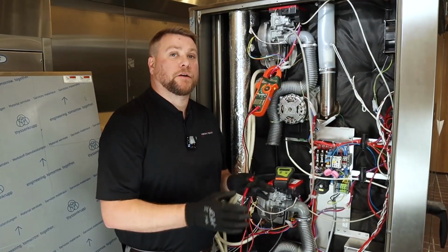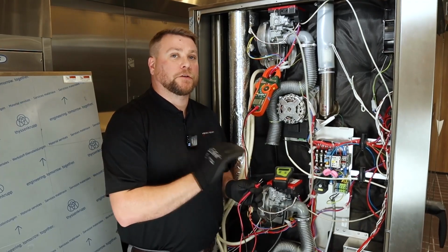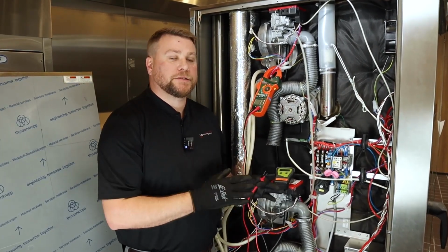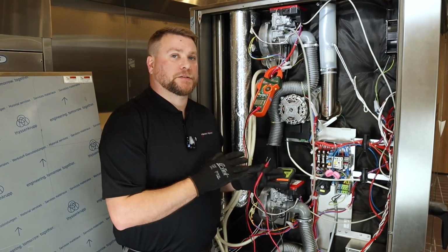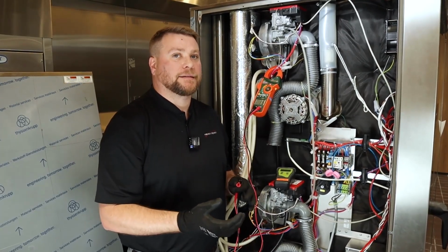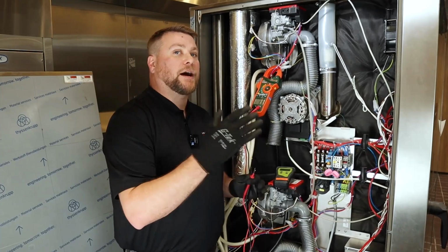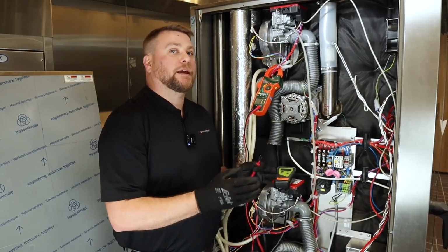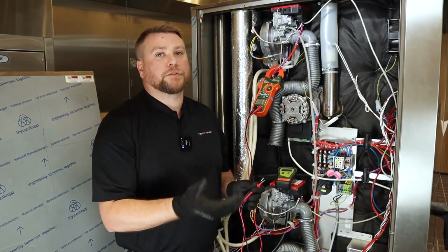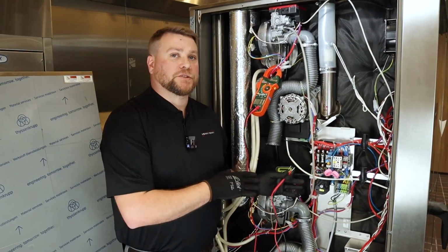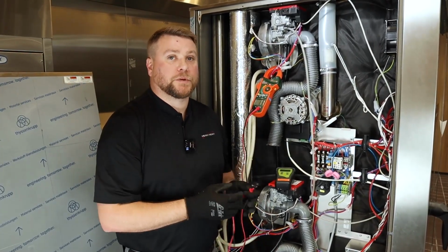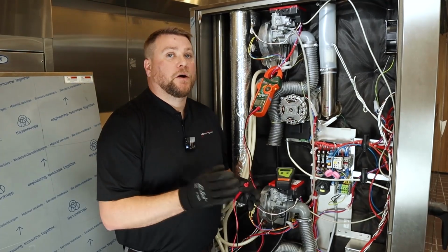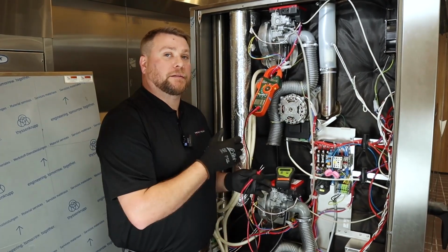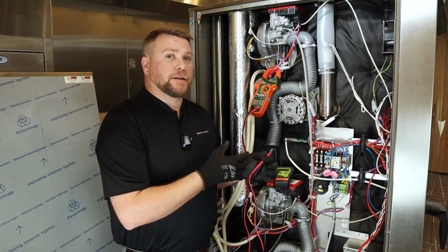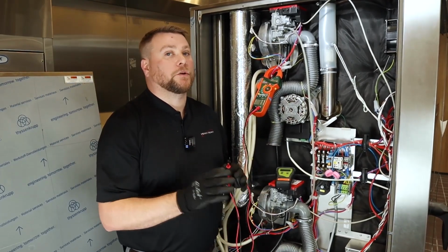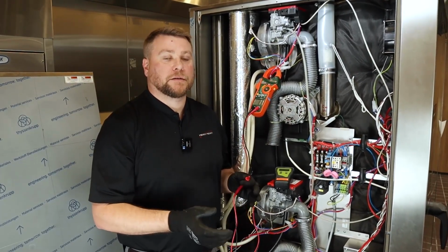Now that we've verified that our glow electrode is good and we are looking for that 1 to 6 ohms on the range, remember that we want to check that when it's cold, because if we check it when it's hot, the problem we run into there is it can give a higher reading on the resistance, and we could end up replacing a glow electrode that really doesn't need replaced after all. So remember to check it cold. Anything above 6 ohms would end up being faulty and need replaced. Also, we could check the amp draw on it by cutting a couple of the zip ties and then using our amp clamp to check amp draw. We're looking for 1.4 amps at least there.